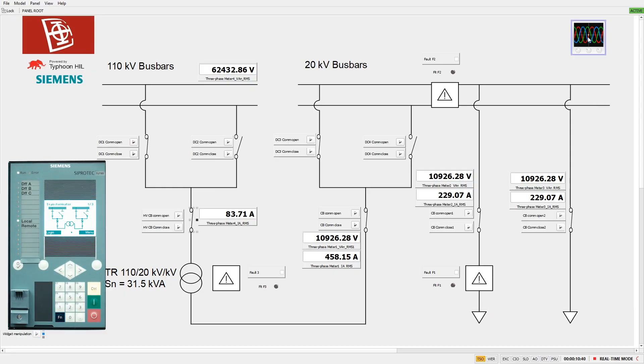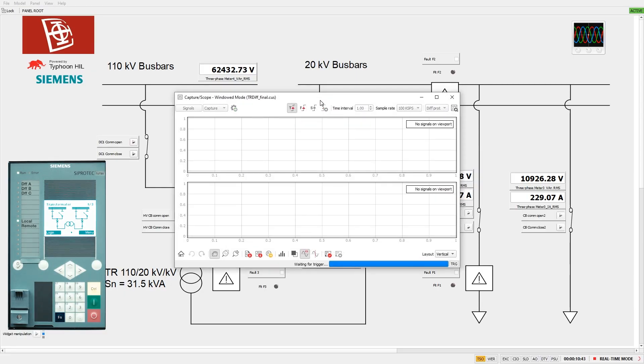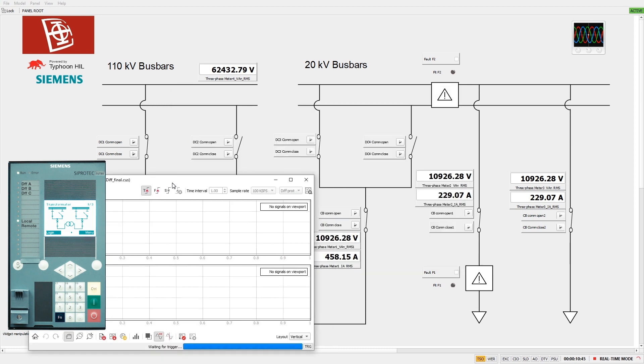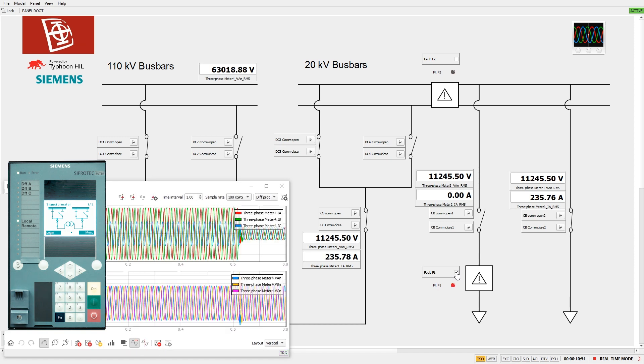In the event of a fault in the feeder, the feeder overcurrent protection picks up, blocks the bus bar overcurrent protection, and trips the feeder circuit breaker after 600 milliseconds.